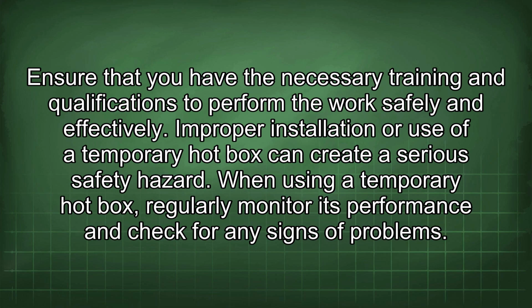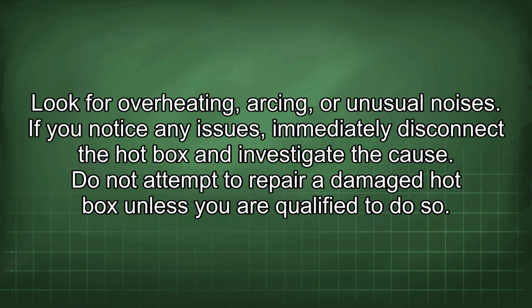When using a temporary hotbox, regularly monitor its performance and check for any signs of problems. Look for overheating, arcing, or unusual noises. If you notice any issues, immediately disconnect the hotbox and investigate the cause. Do not attempt to repair a damaged hotbox unless you are qualified to do so.